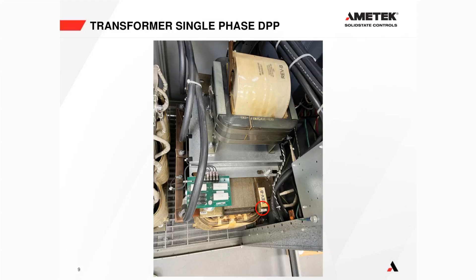And basically, a general rule of thumb is the larger the cable connected will give you a good idea of which is the primary and secondary, because as the voltage gets stepped down, the current is going to go up on the secondary. So you're always going to see larger cables on the secondary, because it carries more current than the cables going to the primary.